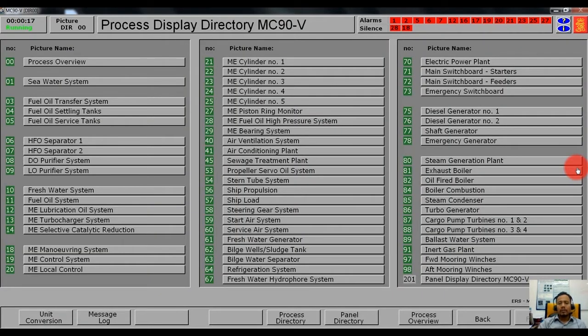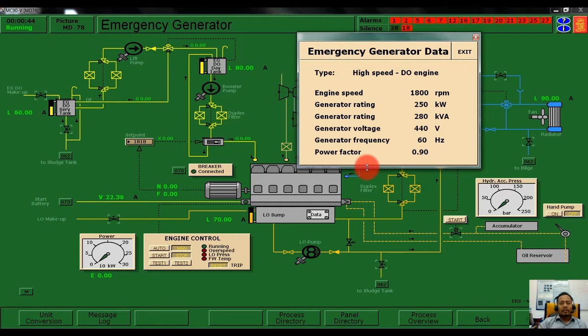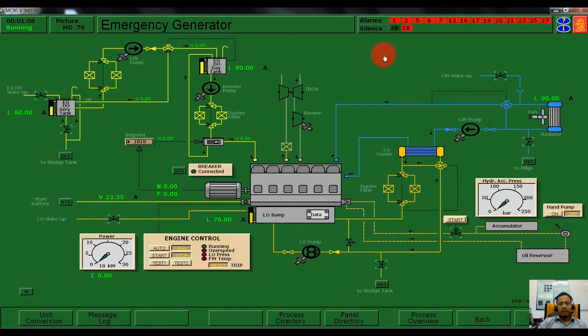Hi everyone. Today we will discuss how to start a ship from a cold start. We need to start the emergency generator. This is our emergency generator configuration. The engine speed is around 1800 RPM, generating 250 kilowatts or 280 kilo volt-amperes, voltage 440 volts, frequency 60 hertz, power factor 0.9. As you can see, this is our emergency generator.